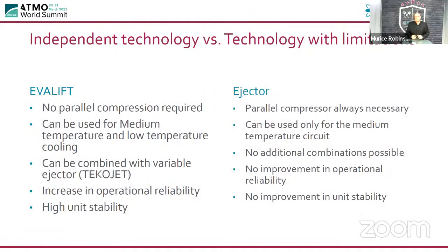So, with regards to independent technology versus technology with limitations: with EVALIFT, there's no parallel compression required. It's not necessary at all, like I explained. With ejectors, you have to have parallel compression. EVALIFT can be used for medium and low temperature, whereas ejectors can only be used for medium temperature circuits. The EVALIFT can be combined with a variable ejector. We've also got a system called TEKOJET that we can install with EVALIFT, which will give you that added extra energy saving. And there's an increase in operational reliability, whereas with the ejector there's no improvement; the operational reliability just stays the same. And there's high unit stability, which is an important part for any retailer or end user. With the ejectors, there's no improvement in the stability of the system.